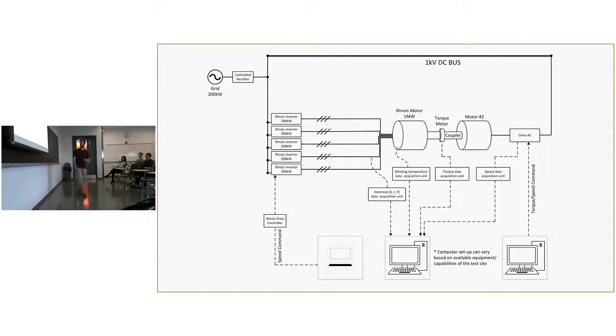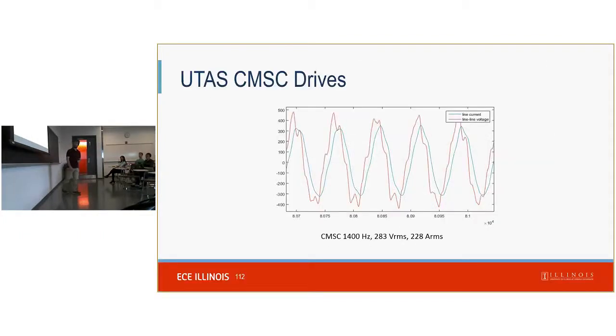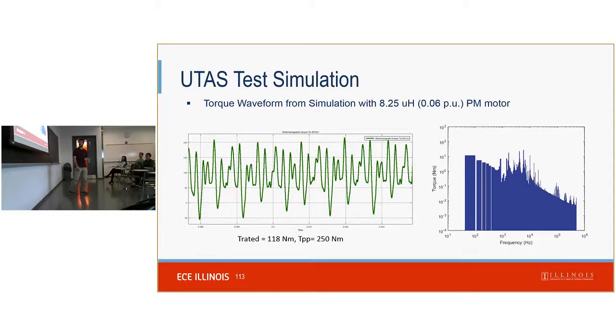So this is showing a little bit, there'll be a 1 kV DC bus to recirculate the power. However, like I said, we'll be using the drives that were designed for the Boeing 787, and those were not designed for 2.5 kilohertz fundamental operation. Their switching frequency is not nearly as high as the drive being developed by the Palawa group, and the applied voltage is not nearly as clean of a sine wave. And so the concern with that is the harmonics, and the current harmonics there are dramatically higher than the motor was designed for.